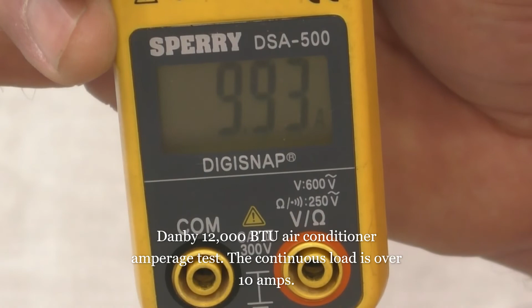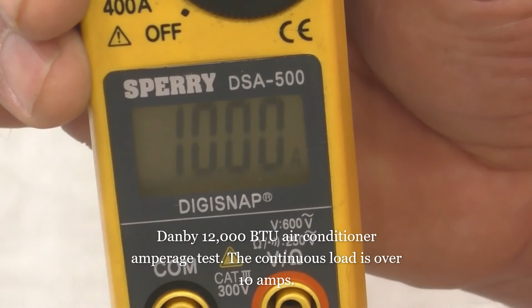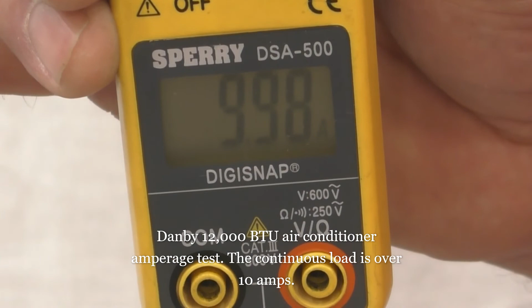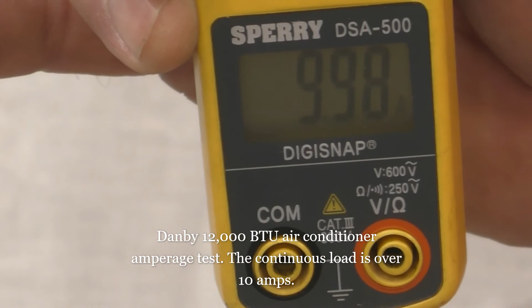Dedicated 20 amp circuit breaker for this unit or any other unit at this time. Anything over 5,000, anything over 6,000 BTUs, you should have it. And plug-in heaters, the floor space heaters that take a lot of wattage, need a 20 amp dedicated line. I can't say it enough. Do it.